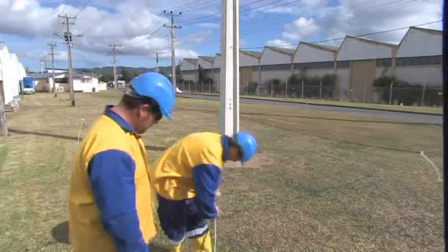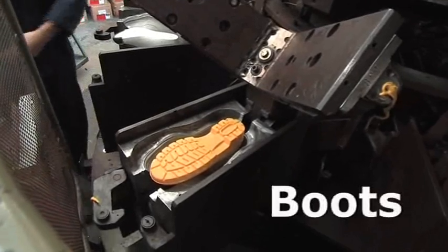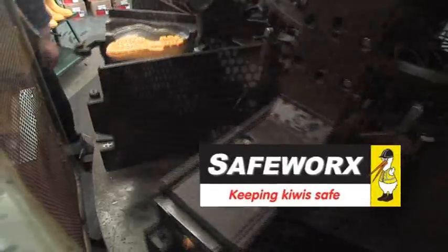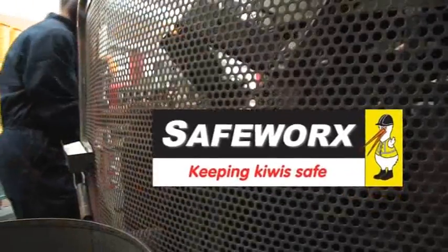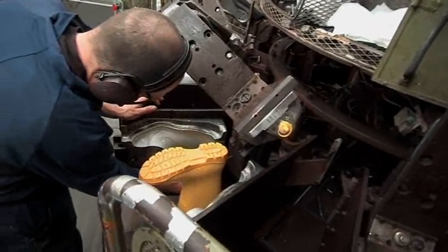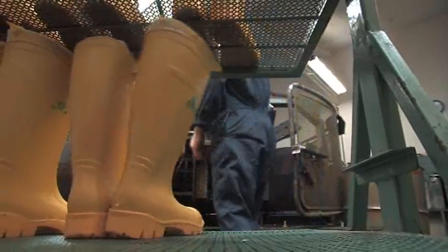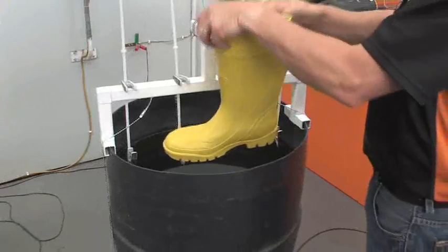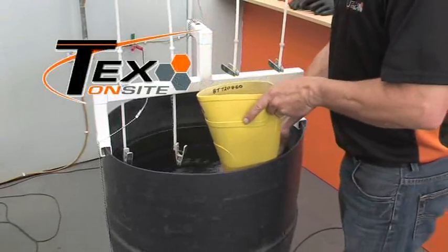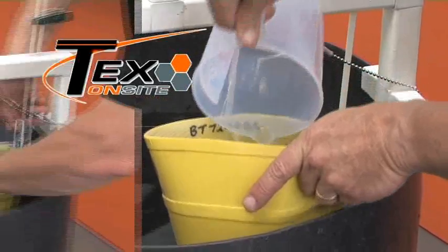Creating a barrier around the work area prevents those without dielectric footwear from entering an area where there may be a risk of step potential. The dielectric boots are manufactured locally and sold through Safeworx. They have steel reinforced toe caps as well as sole inserts for comfort. Before they were accepted as suitable to this purpose, TEX OnSite conducted stringent tests on the boots, subjecting each one to 10 kV for one minute.